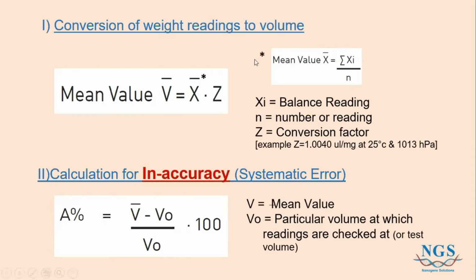Once you have your mean value X bar of each volume, you want to find the mean volume, V bar, for each testing volume as well. You will use the mean value X bar times the conversion factor. The conversion factor is probably fixed if you're using distilled water. For example, with distilled water, it will be 1.004. So as simple as that, you'll find the mean value V bar of each testing volume: the maximum, the 50%, and the minimum value. Once you have that, I will be calculating 2 things, the inaccuracy and imprecision.